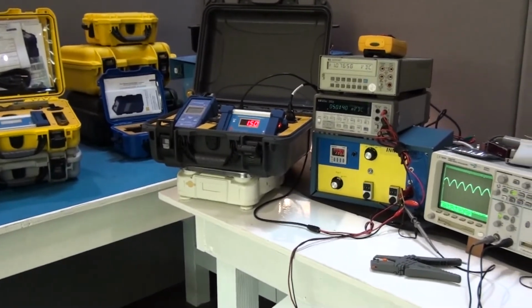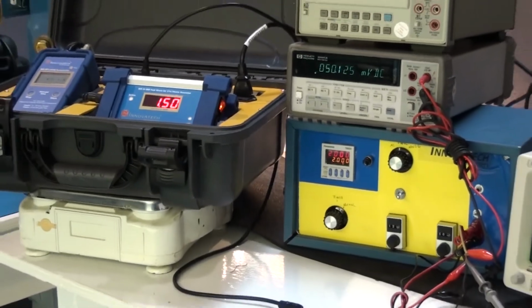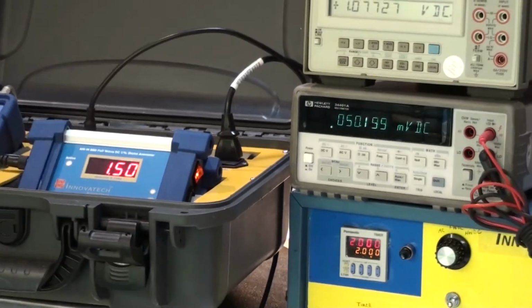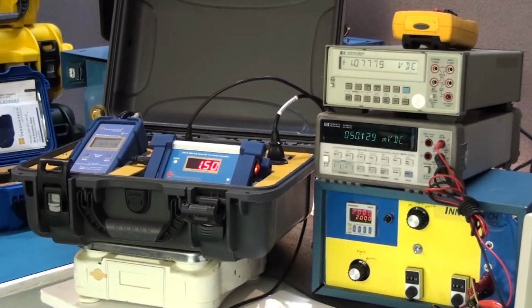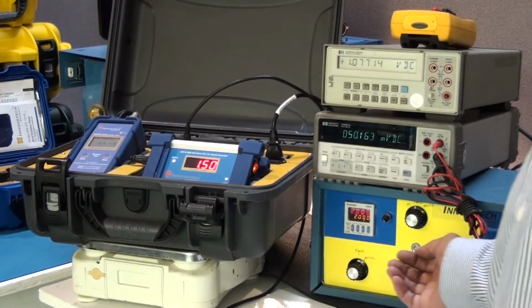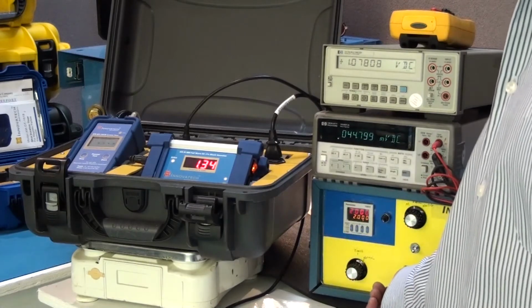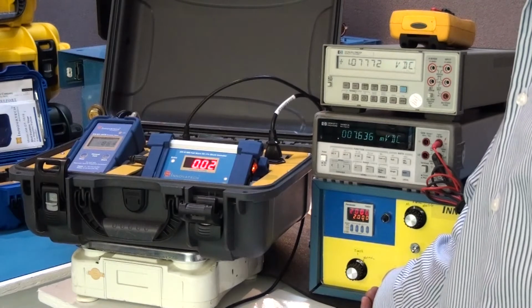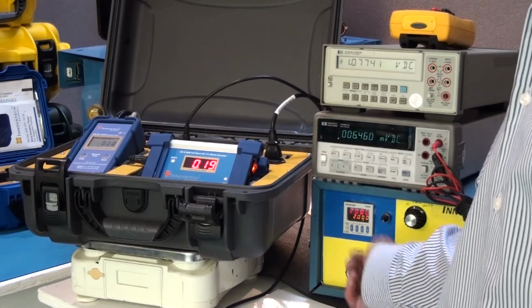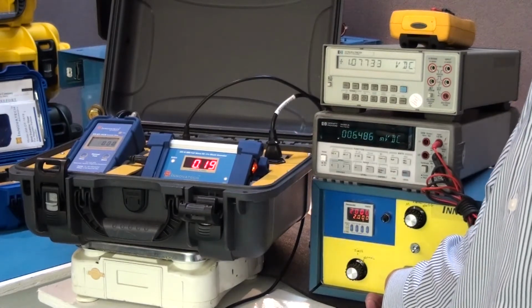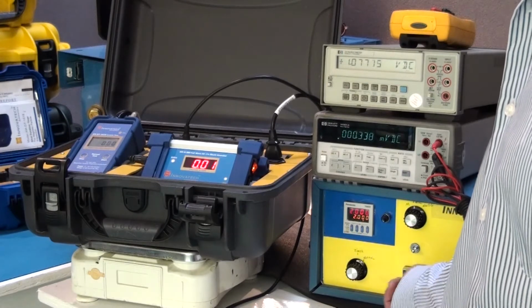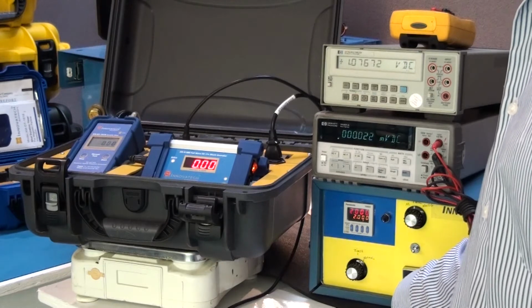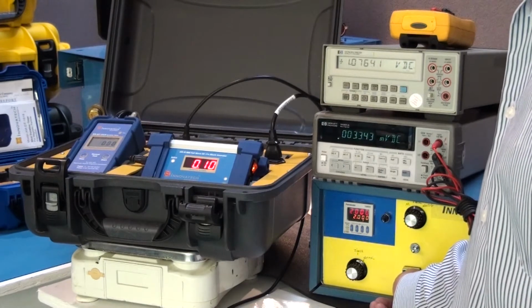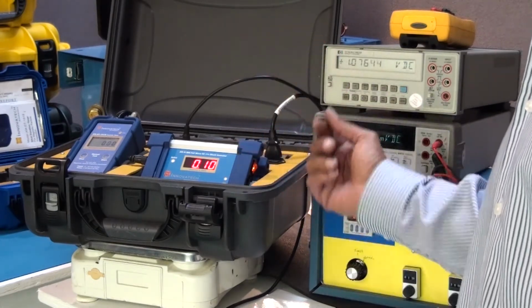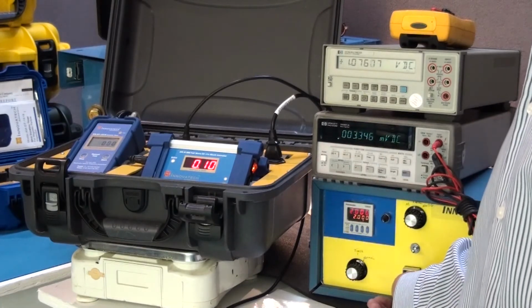Okay, so we want to confirm calibration. We'll run this down to 100 amperes here. This is times 1000. So we're going to go to 3.3 millivolts, as this is calibrated for 50 millivolts to 1500 amp shunt. And here we'll turn this to 3.3 millivolts. And you can see here that we have 0.1 times 1,000 is 100 amp, and 3.3 millivolts.